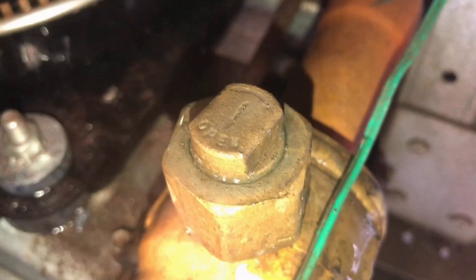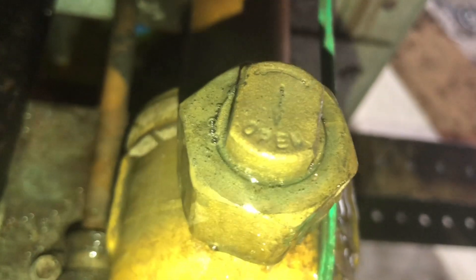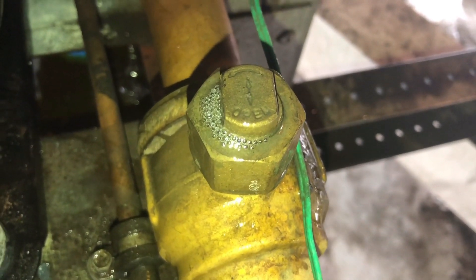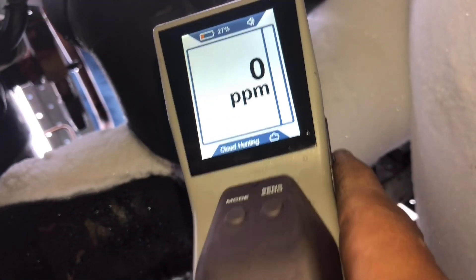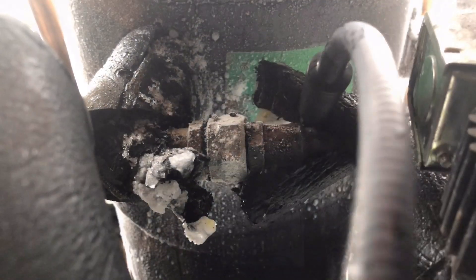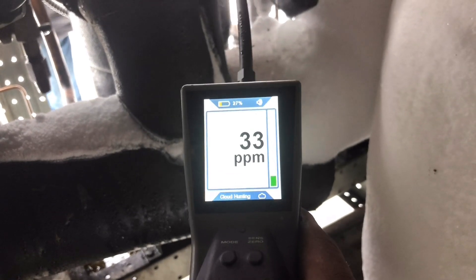All right, so the bubbles — that's the leak that the Stratus was picking up right there. The Deep Tech Stratus was picking up — look at that. There it is. Big spot the Stratus is picking up — got some bubbles forming. Another leak right here. There's something going on there.